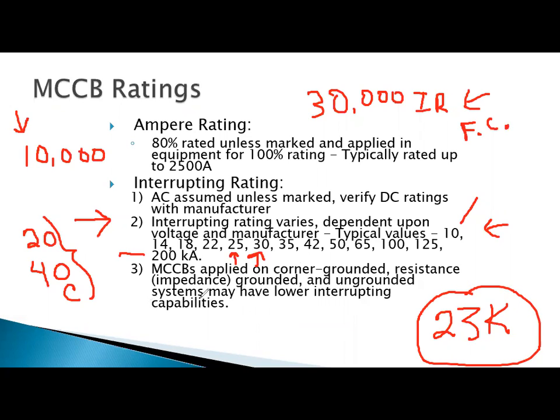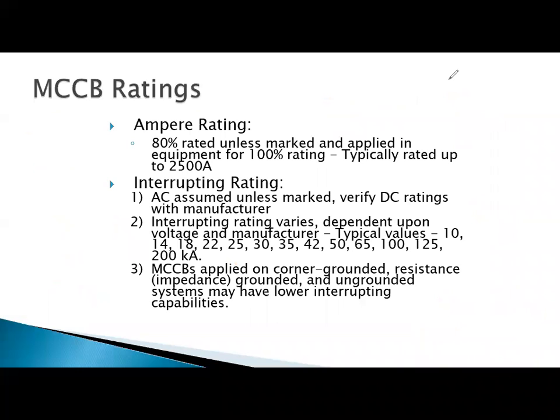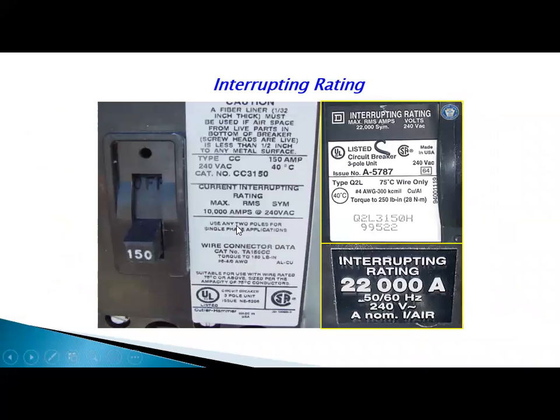Now, on some different systems, which they're talking about here, some corner grounded delta systems or maybe some resistance or impedance grounded systems, they could have a lower interrupting rating because we are limiting the amount of ground fault current with these different types of systems. So I want you to really remember about interrupting rating on the side of our breakers. Extremely important. And we're going to be able to see a couple here. So this is a 150 amp breaker on this side, but its interrupting rating is 10,000. Over here, we have a different rating on the breaker.